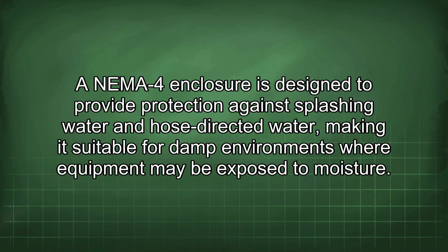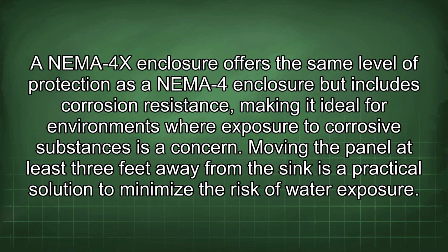A NEMA 4 enclosure is designed to provide protection against splashing water and hose-directed water, making it suitable for damp environments where equipment may be exposed to moisture. A NEMA 4X enclosure offers the same level of protection as a NEMA 4 enclosure but includes corrosion resistance, making it ideal for environments where exposure to corrosive substances is a concern.